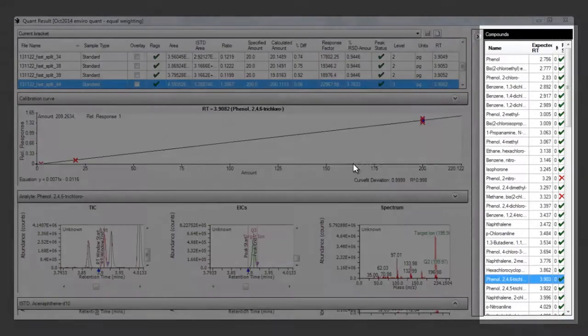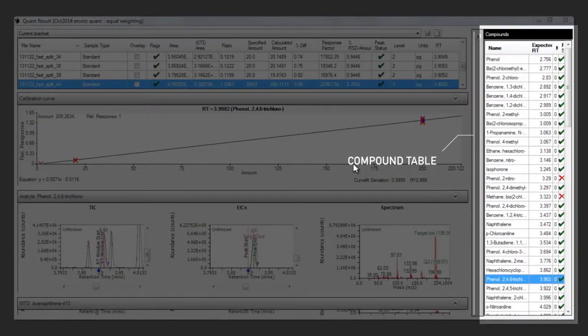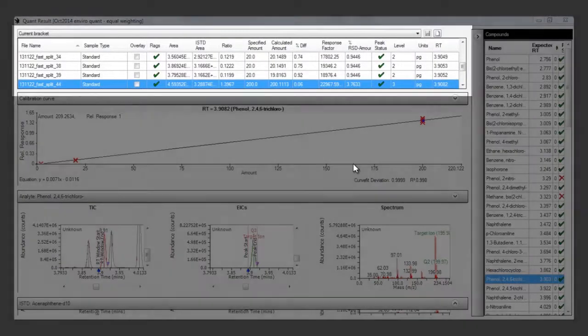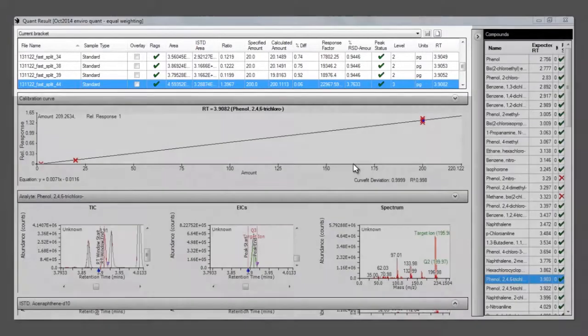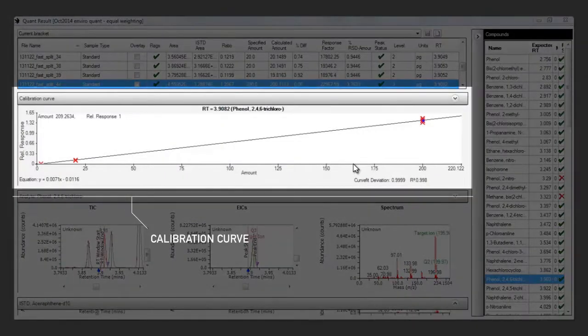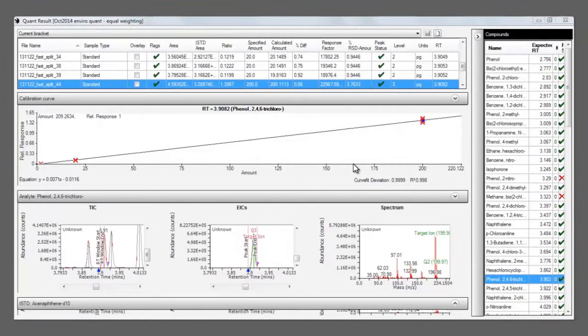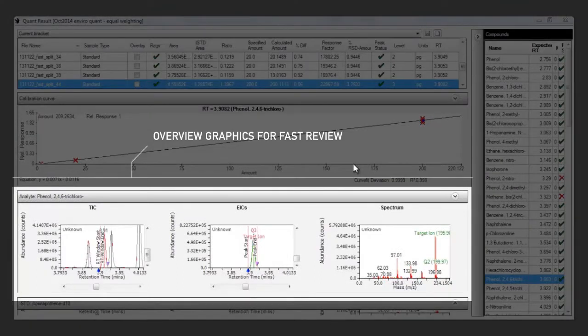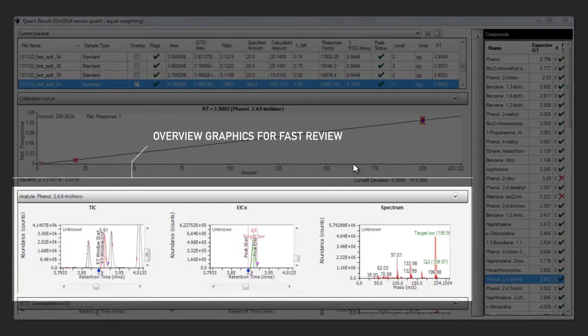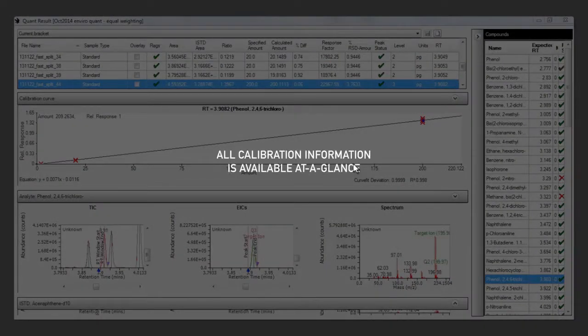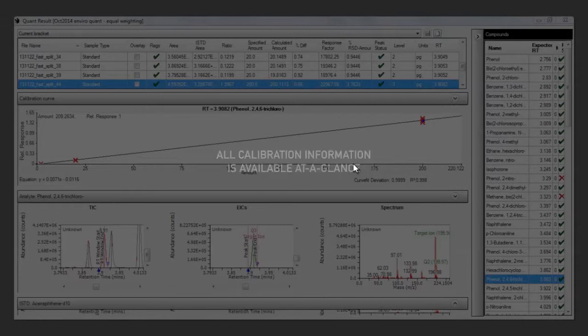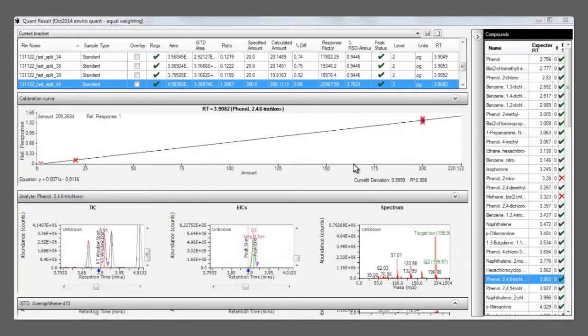On the right is the list of quantified compounds. At the top is the list of samples, in the middle is the calibration curve with the equation and R-squared value, and at the bottom are the same TIC, EIC and spectrum graphics that we saw when setting up the quant method. Combined with the suitability flag system, this layout allows users to quickly review the calibration information in a single screen.